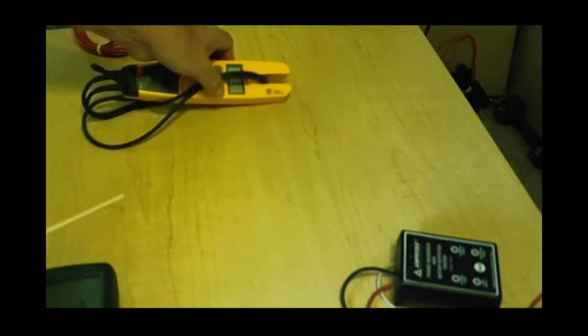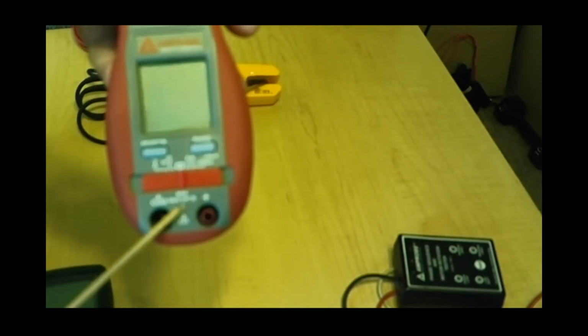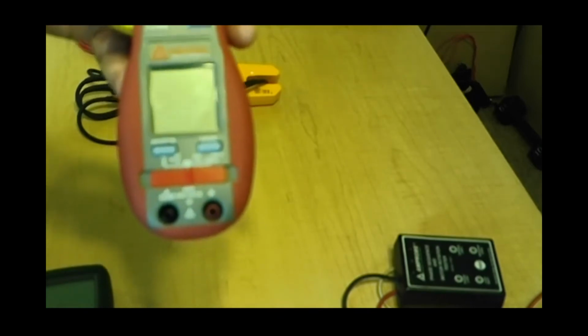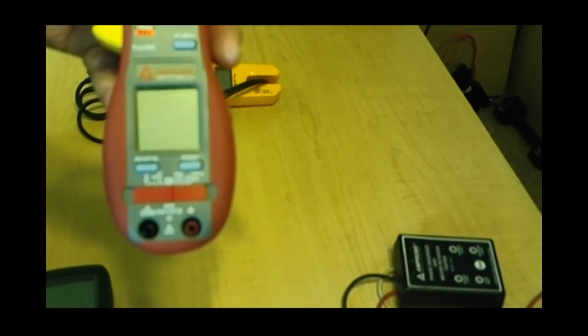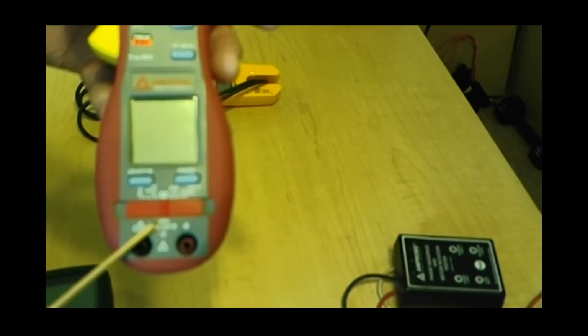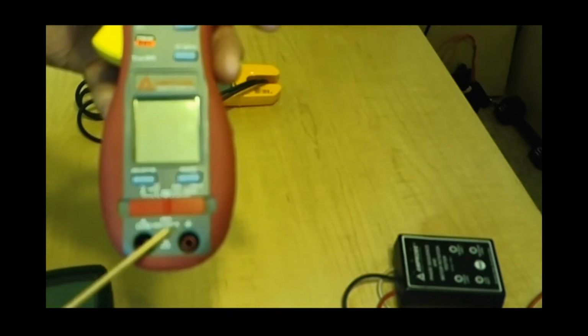But now the Cat 3 meters are a little bit different. We take this meter labeled Cat 3, Cat 3 600 volts. Cat 3 meters are only designed to be used indoors only, downstream of the service equipment. So this is general use anywhere in the building except for service entrance. So you would not use Cat 3 on a switch gear or main panel coming in. That'd be a Cat 4 location. This is everywhere else throughout the building.